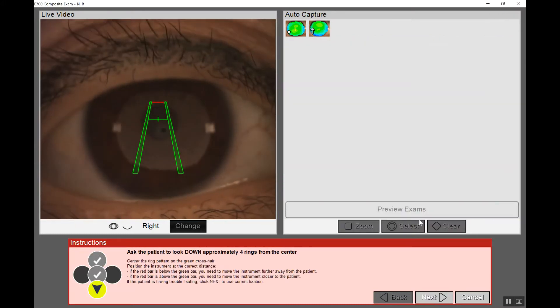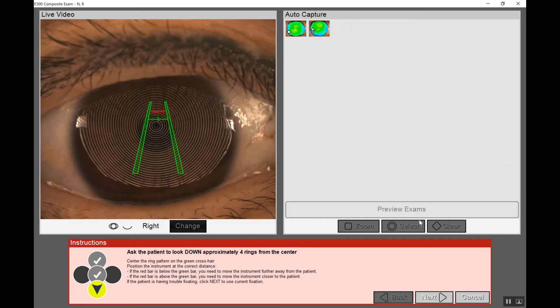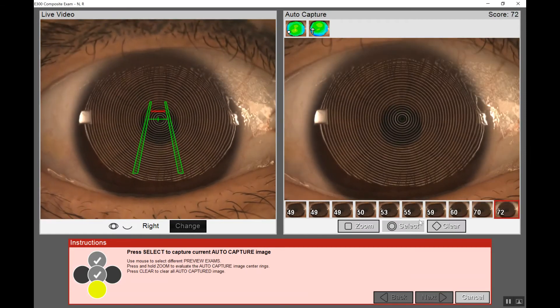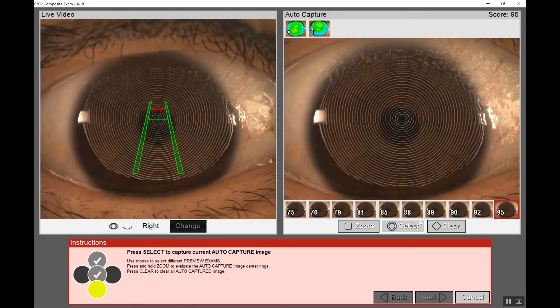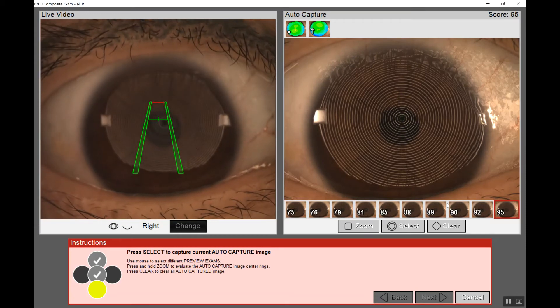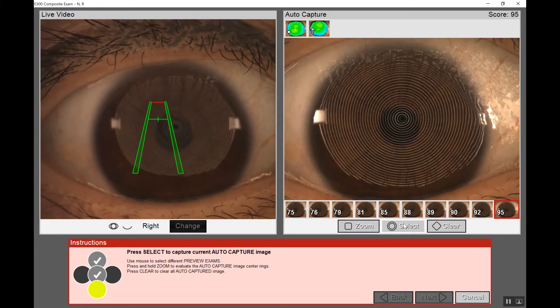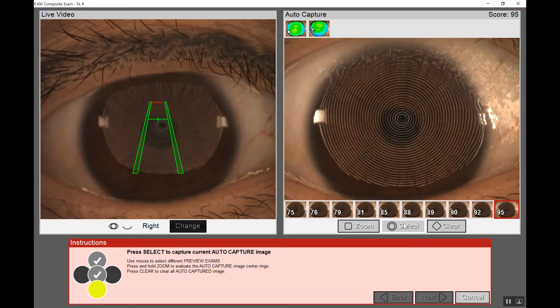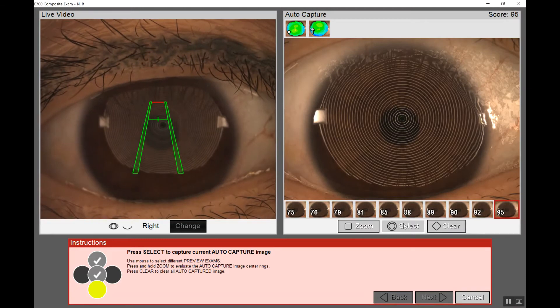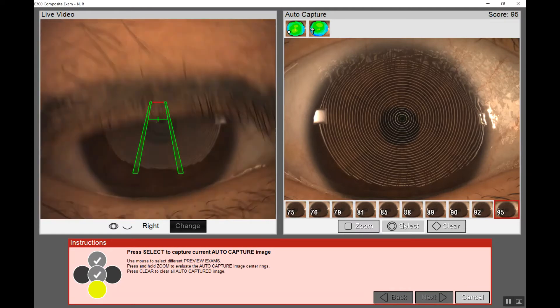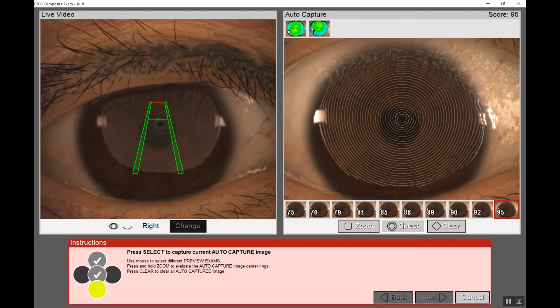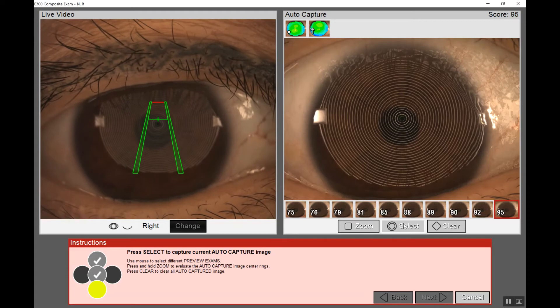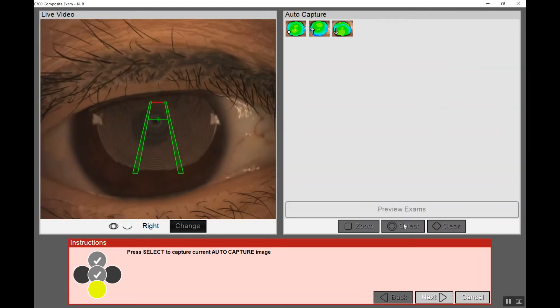Next the software will say ask your patient to look down approximately four rings. Here we may need to ask the patient to open up as wide as they possibly can. Try to expose that superior cornea so we can get the rings to 12 o'clock and our patient has done a good job of opening up as wide as possible. We were able to get a 95% with the rings reaching the superior cornea. We can zoom in, ensure those central rings look parallel and even. If so we can click select. Now this is the trickier of captures because with the patient looking down that could mean the upper lid is in the way, and if that's the case then have the patient reach above the instrument and pull up on their eyebrow. In this case we were able to simply expose the superior cornea by asking the patient to open up as wide as they possibly could. Let's click select.